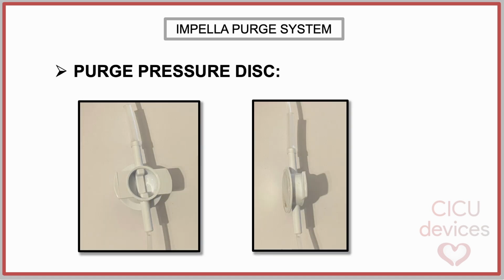Structurally, the purge pressure disc consists of a flexible diaphragm and an interface region that couples mechanical deformation to the internal pressure sensing system of the console. This way, the purge fluid does not come into direct contact with electronic components.